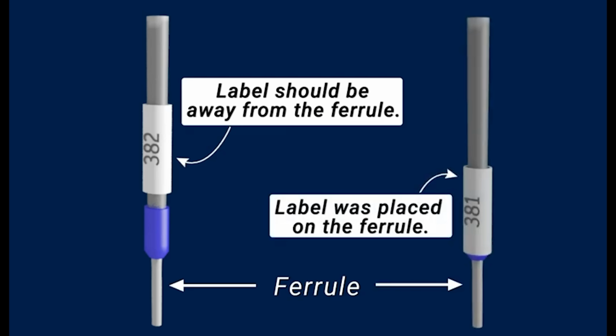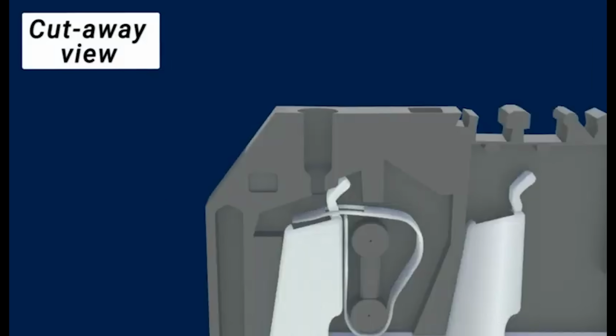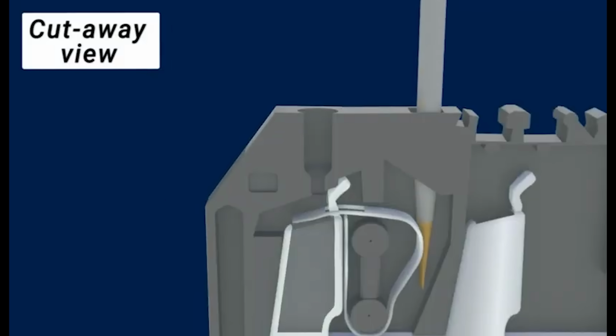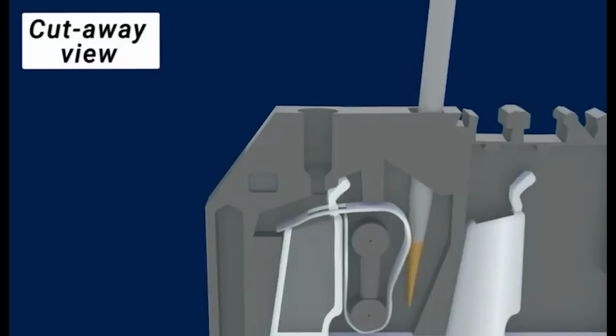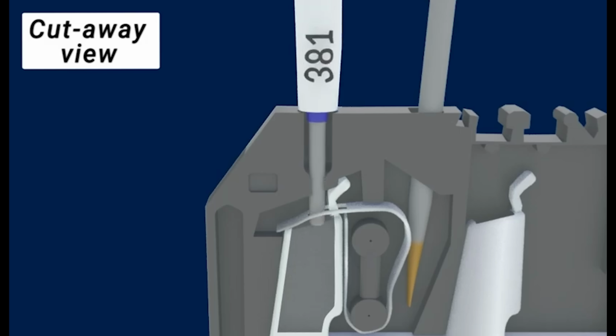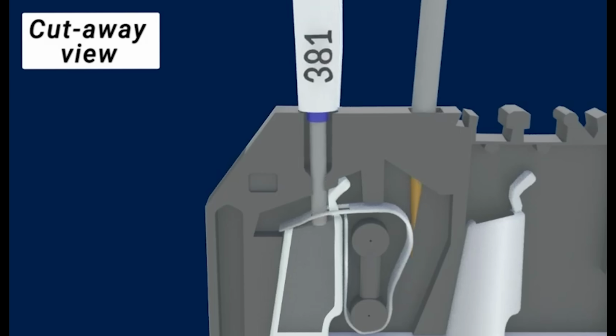But guess what? Many of the labeling bands on the Dali wires were placed partially on the ferrules, which actually increases the ferrule's overall circumference. Because of this error during construction, some of the ferrules could not be fully inserted into the terminal blocks, including this ferrule here on wire 1 from terminal block 381. Let's see how this error with the thicker plastic affected it. So on that wire, the labeling band prevented full insertion of the ferrule so that the spring clamp actually gripped only the ferrule's tip, resulting in an inadequate connection.